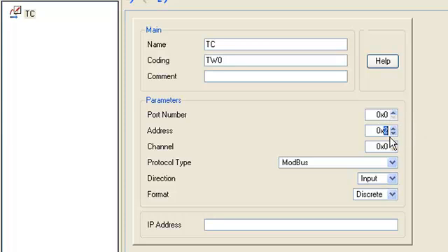The setting channel is the starting address of the input register must be set to 0, because number 3 is the data type identifier and the minimum starting address in Trace Mode is 0. Standard Modbus starting address minus 1.